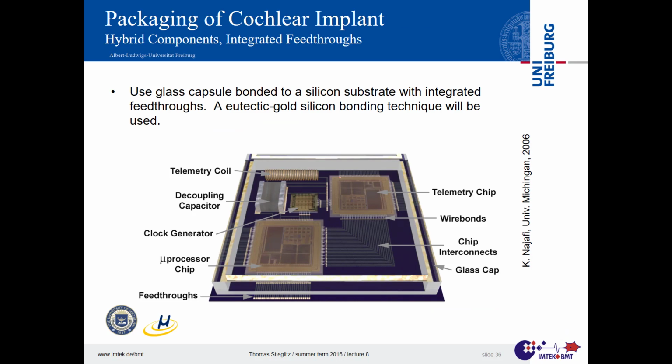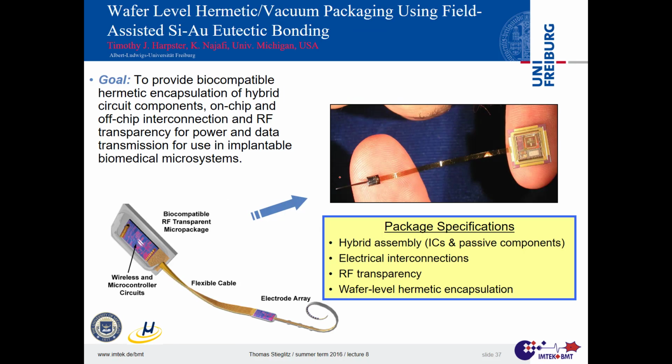And they wanted to make a new kind of cochlear implant, so more complex, smaller, whatever. And I always have to smile on those slides. Really excellent work from the electronics side, but I would doubt a little bit that a medical doctor likes those sharp edges and corners of the package wall. So this is what I learned. If you have something like that, you should put it in something more round, so that surgeons are happy with you and don't see the edges and corners.